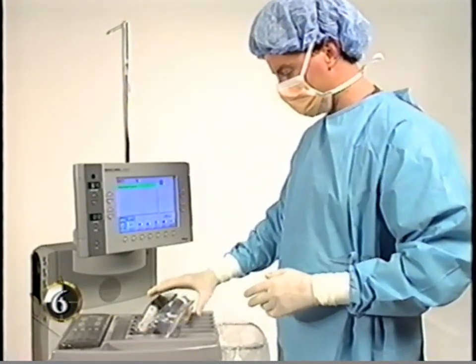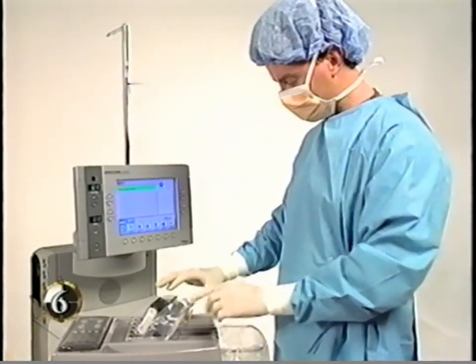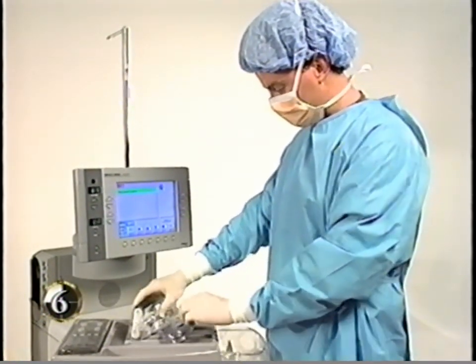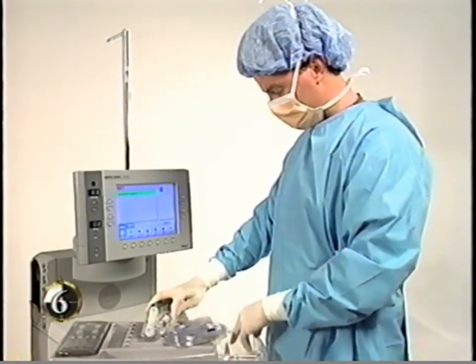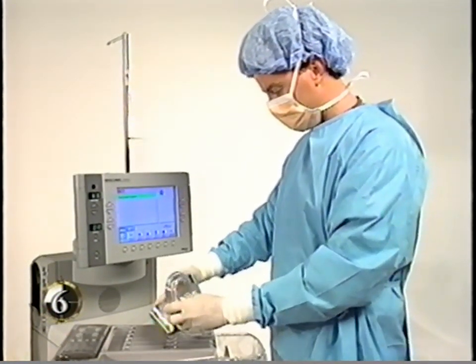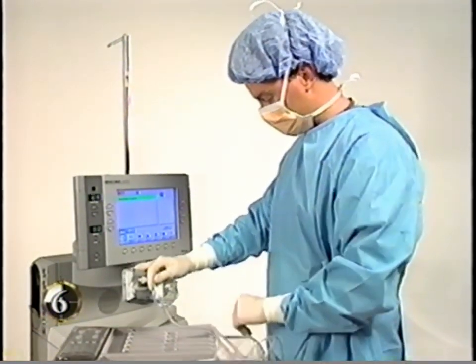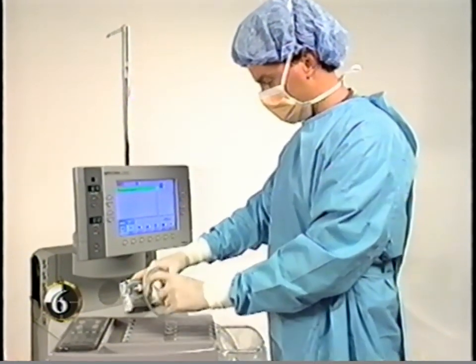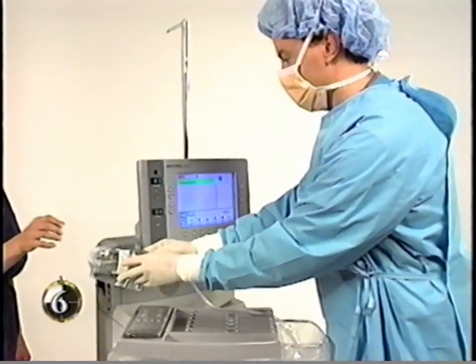Transfer the remaining components of the cassette pack onto the instrument tray. Break the paper band on the irrigation and aspiration tubing and uncoil the top portion. Place it in the tray. Hand off the cassette and irrigation line with drip chamber to the circulator.